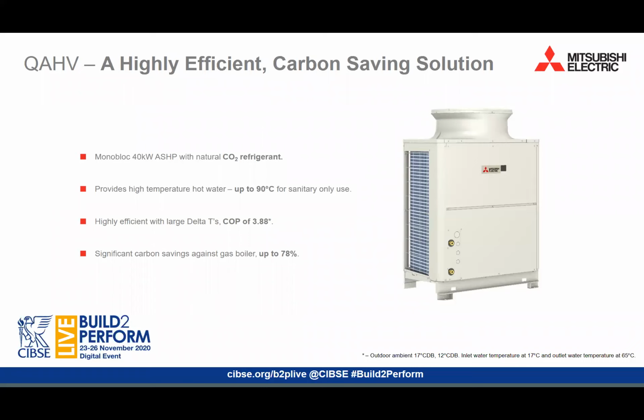Commercial heat pumps, such as Mitsubishi Electric's CAHV, have always been very efficient at providing LTHW for space heating, but struggle to show the same level of carbon saving when producing sanitary hot water at higher flow temperatures. Seasonal efficiencies of the QAHV producing sanitary hot water at 65 degrees Celsius have been calculated to be between 3.2 and 3.5, depending on the location, which when compared to a typical gas boiler can show carbon savings of more than 78%. A subject we'll expand on later.